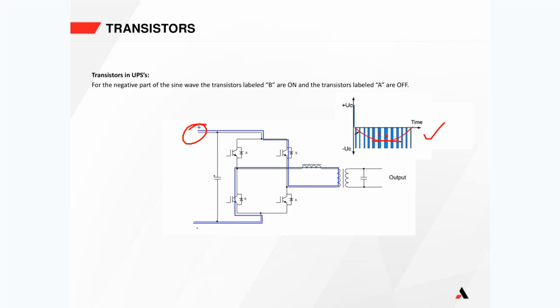Or if the DC voltage starts going down, which would make the amplitude of this start going down, then we can widen the pulses instantaneously as well. Using feedback, we make sure that the output of this UPS, if it was a single phase system, this output here would be 120 volts at all times. So that is the IGBT, and that is how it is used inside a UPS system.